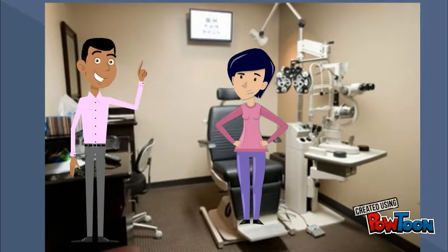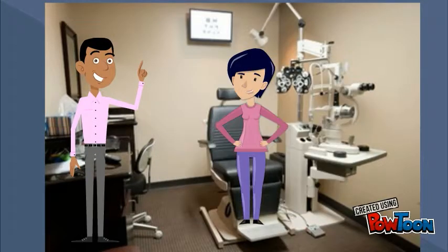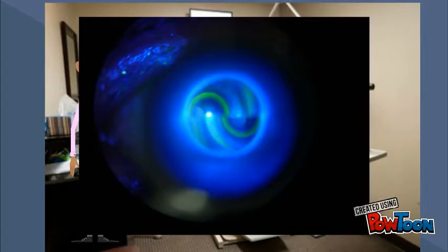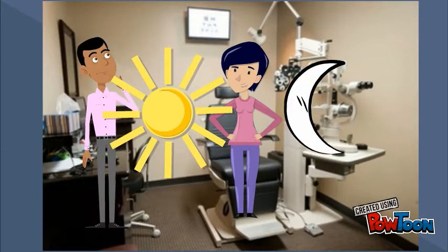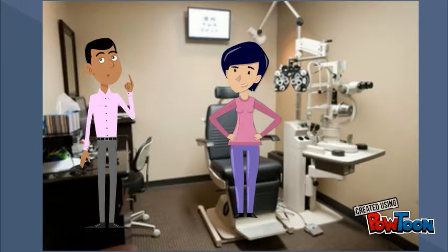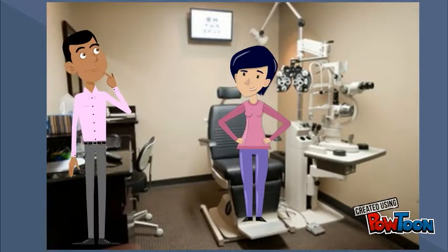The doctor then uses a tonometer probe, which has a biprism that creates two semicircles. When the probe applanates the cornea, the dial on the Goldmann tonometer is manually rotated until the two semicircles just overlap. The pressure is then read off the dial and documented in millimeters of mercury. There is great variance in intraocular pressure among patients from the morning to the evening and inter-doctor differences. Therefore, pressure alone cannot be used to diagnose glaucoma.